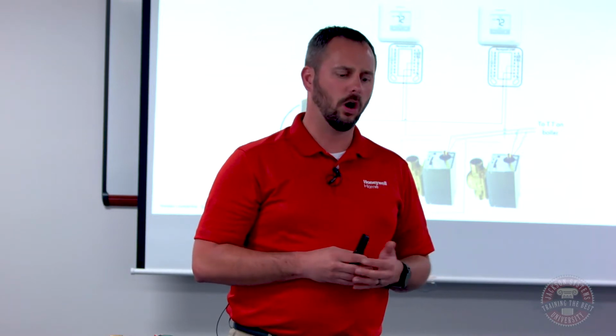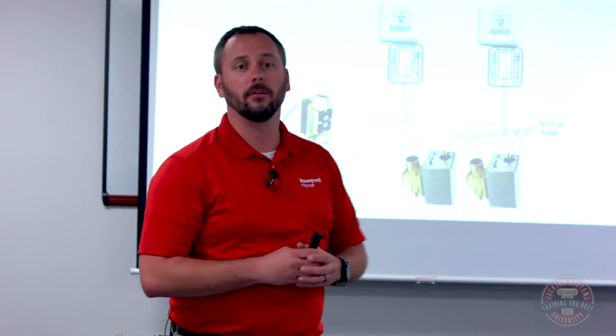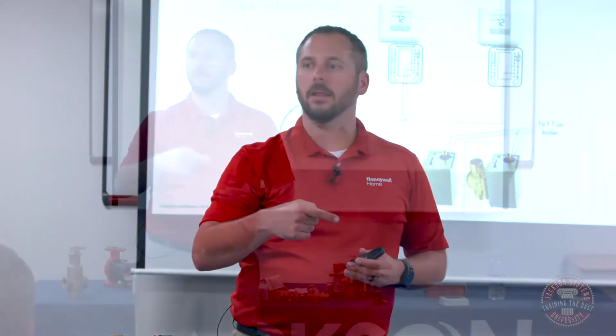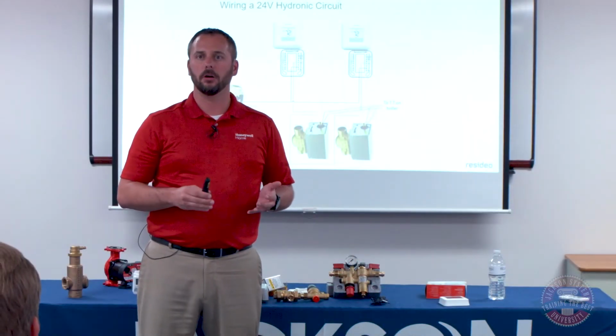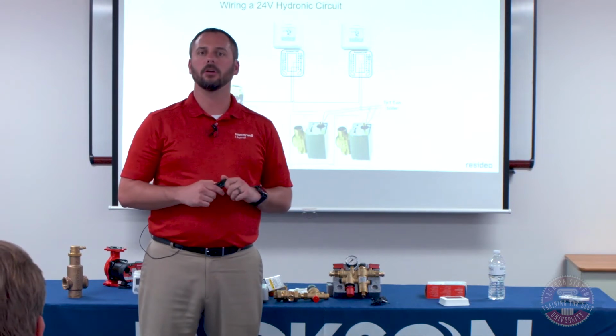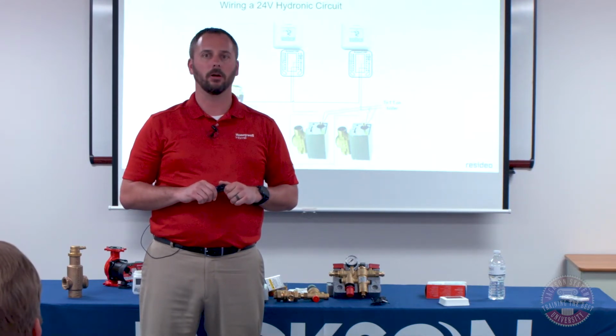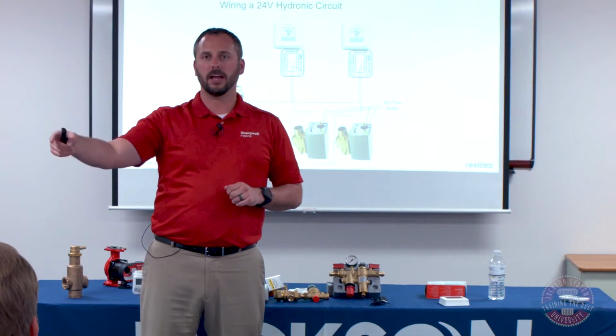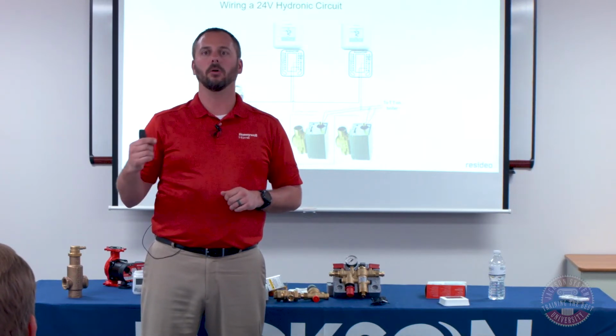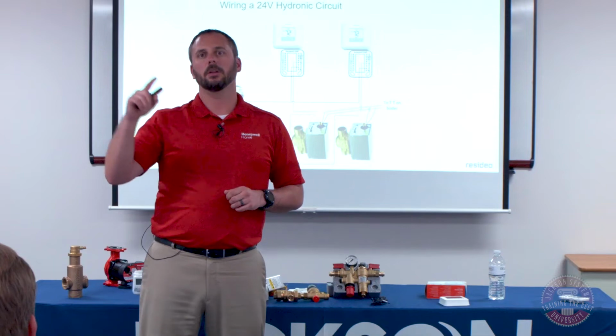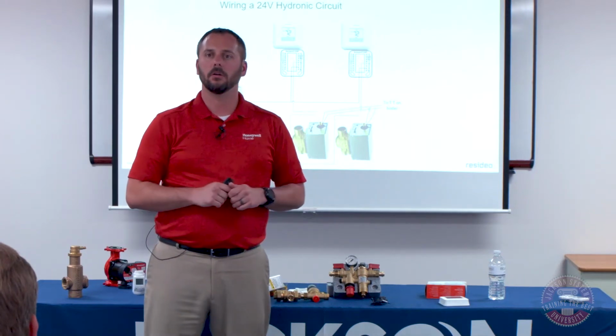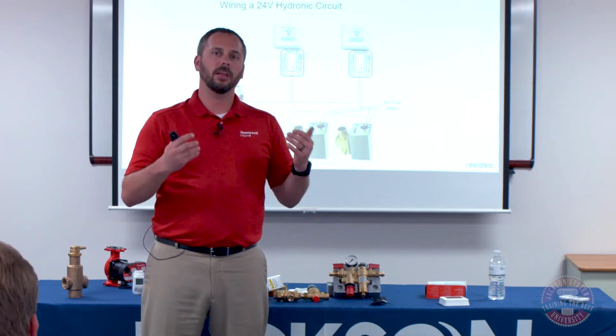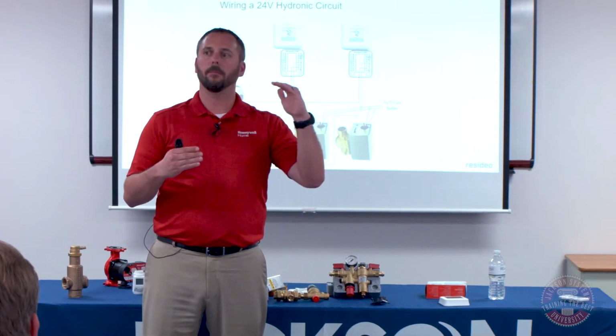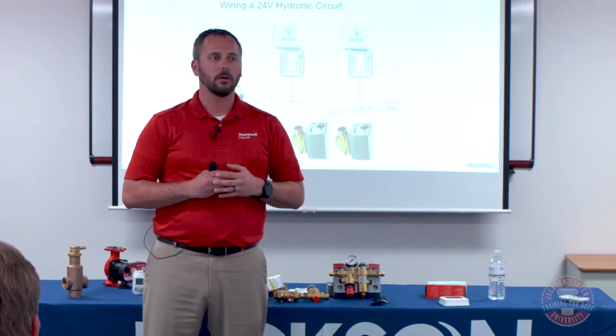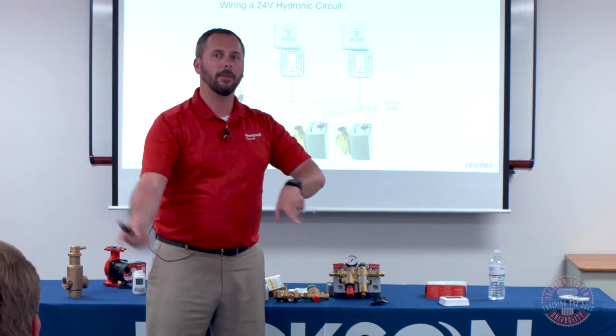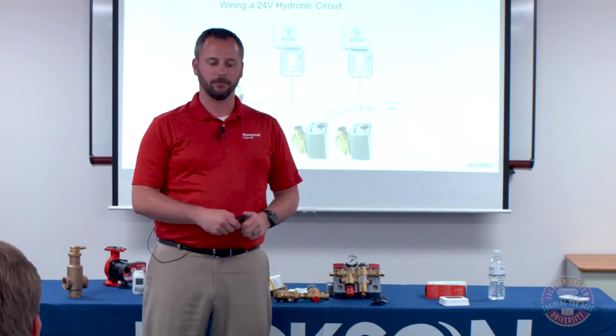So let's say zone 1 is the thermostat on the left and the zone valve on the left. We're going to take W from that down to one side of that motor. That motor has to go back to the transformer. We're going to take the W off the second thermostat and go to the zone 2 motor on the zone valve. Then we're going to take that motor back to the transformer. So think of it as you're loading up both thermostats with power. Where do you want that power to go? And the power has to make it back on both of them.